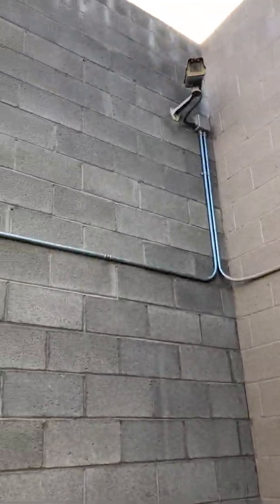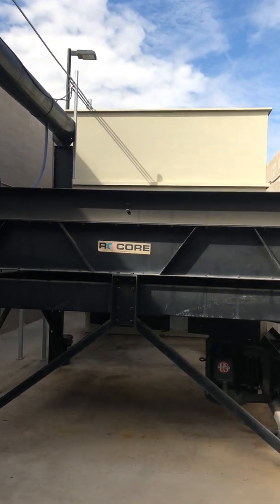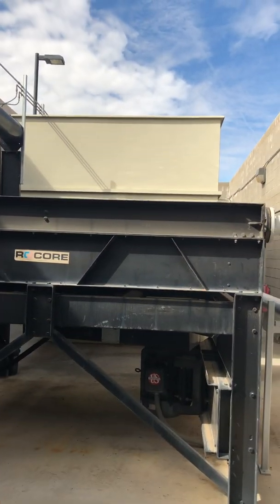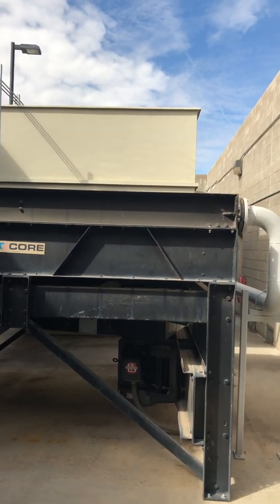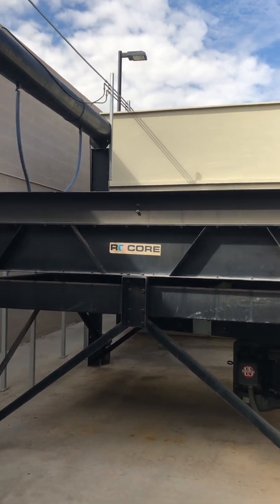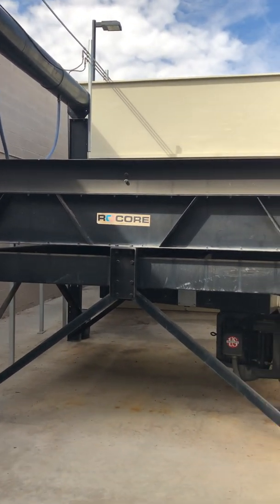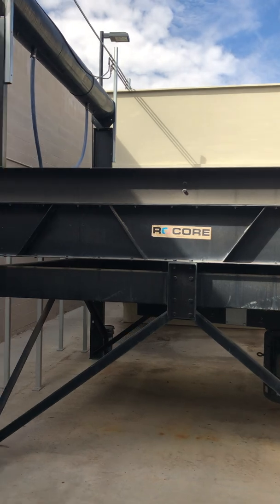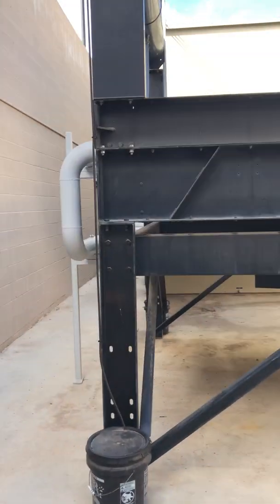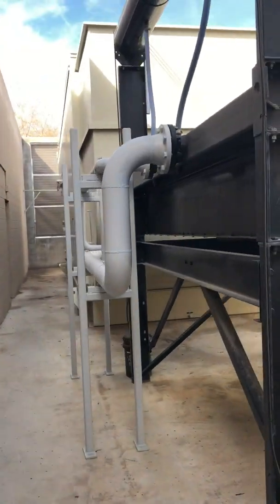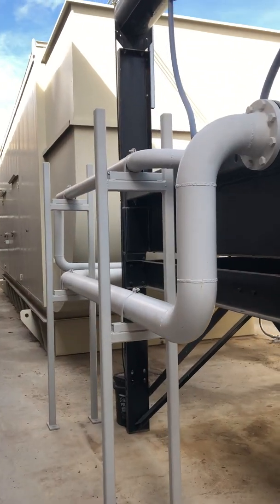The factory generator is not meant for Arizona's high temperature environment, so we have the Rocore refit radiator, which will allow us in the hottest part of summer to maintain power to the site should we lose the SRP feed. As you can see, the core is considerably thicker on the radiator than a traditional factory enclosure radiator.